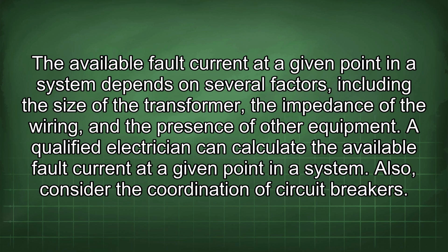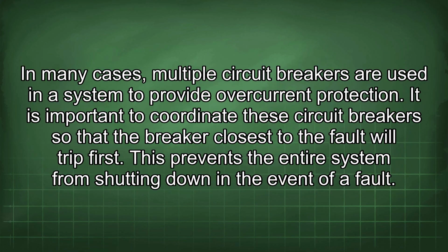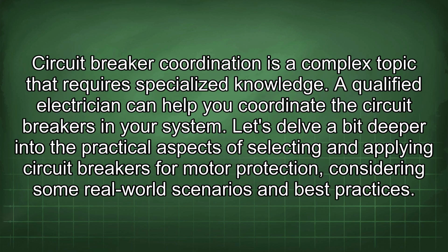Also, consider the coordination of circuit breakers. In many cases, multiple circuit breakers are used in a system to provide overcurrent protection. It is important to coordinate these circuit breakers so that the breaker closest to the fault will trip first. This prevents the entire system from shutting down in the event of a fault. Circuit breaker coordination is a complex topic that requires specialized knowledge. A qualified electrician can help you coordinate the circuit breakers in your system.